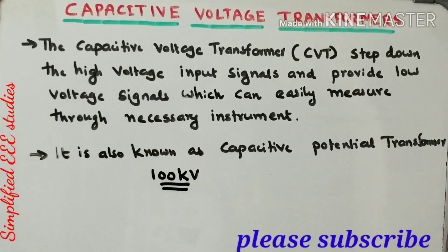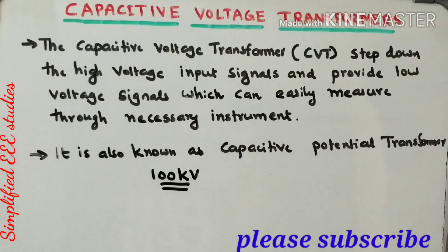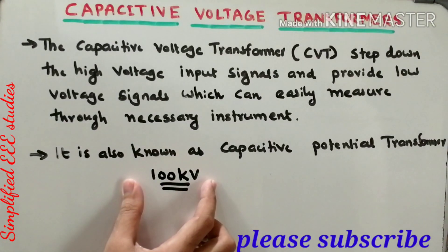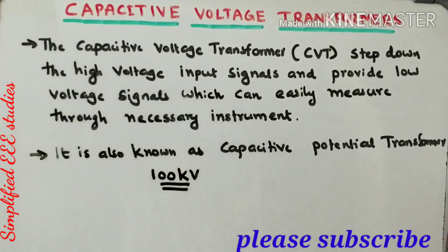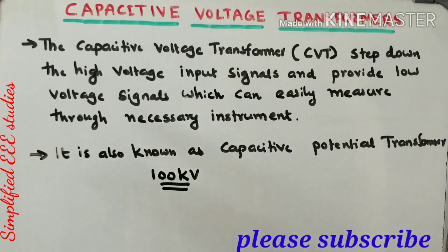It is possible to measure high voltage using instrument transformers such as CT or PT. But the main problem is if you want to measure voltage above 100 kV, we need to provide a very high amount of insulation on those instrument transformers, which is not economically feasible. That is why we mainly depend on the capacitive voltage transformer, or CVT.